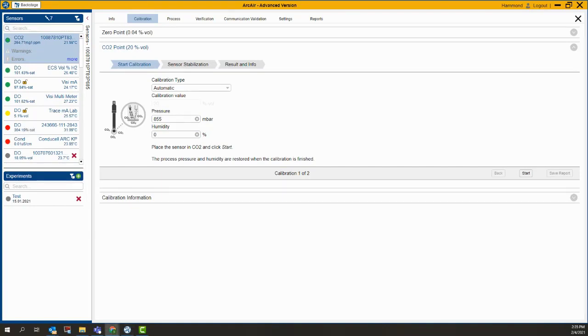So my CO2 has been flowing now for about 5 minutes, and my value is stabilized right around 263 to 265 milligrams per liter. So there's a couple important notes regarding the CO2, and one is that you want to flow with controlled flow rate. So that is a 1/2 liter per minute. And if you're flowing through a flow cell, you want to make sure you don't have any sort of back pressure on the flow cell. Back pressure will increase the density of the CO2, and that will throw off your calibration.